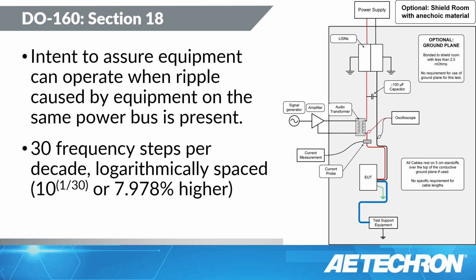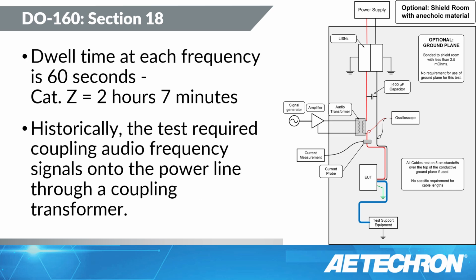Okay, so when you're performing this test, you're doing frequency steps at 30 frequencies per decade, logarithmically spaced. You can see a formula here. These are about 8% step sizes. And you dwell at each one of these frequencies for 60 seconds.